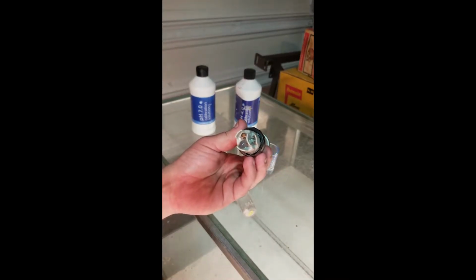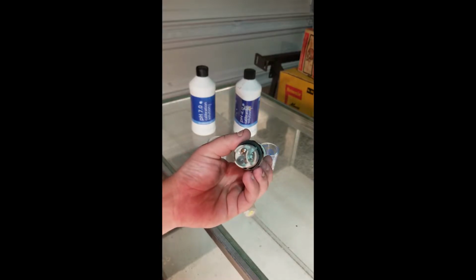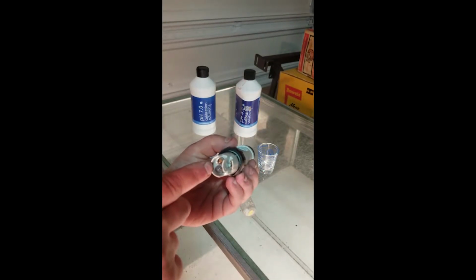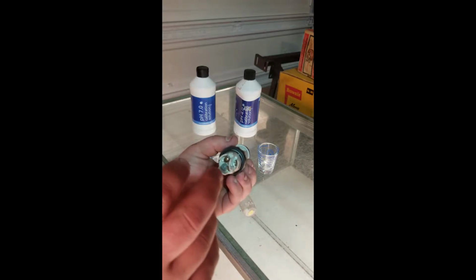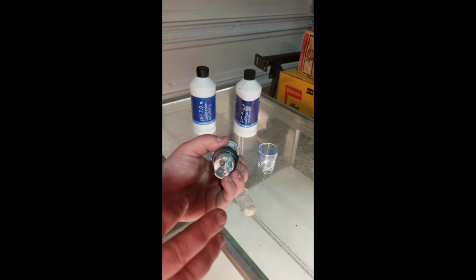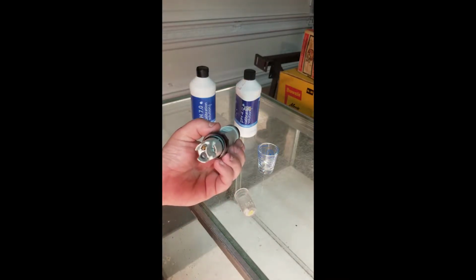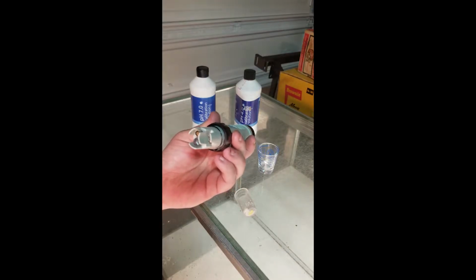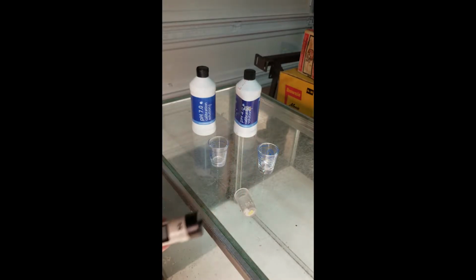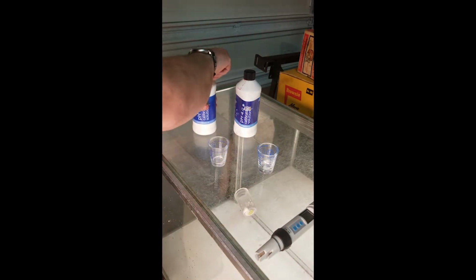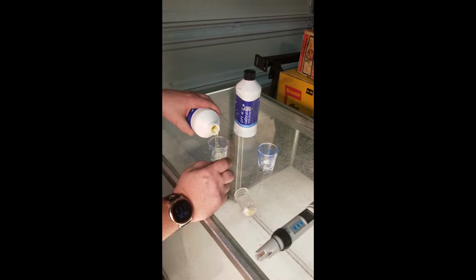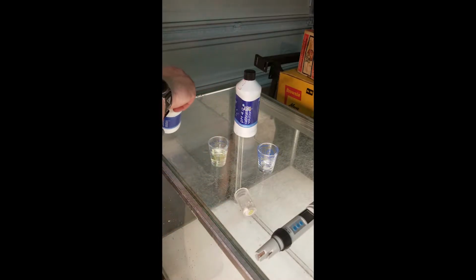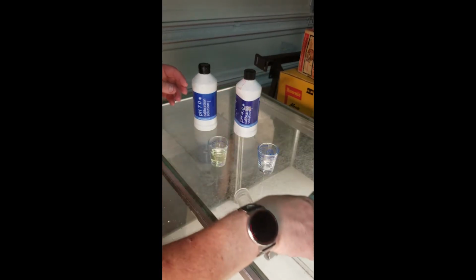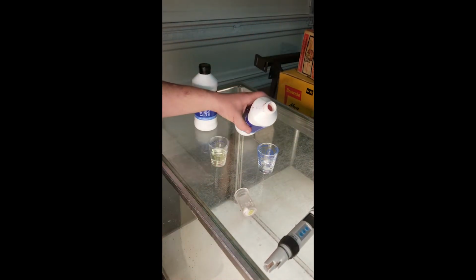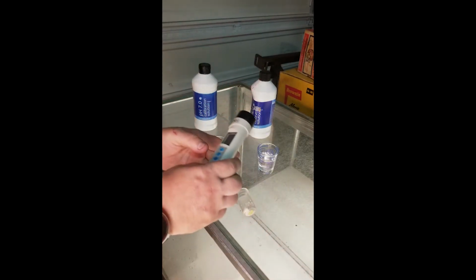First things first, make sure your probes are clean. You can take a very soft toothbrush to get any gunk that sometimes can get built up in the corners of the pH probe. Any physical media from slurry tests or anything like that can actually cause fluctuations and instability in the pH reading. So make sure you clean those tips really good first. Then I'll pour out a little solution that I'll discard in the end, enough to get good saturation so it'll sit down deep, of the pH 4 and the pH 7. They're usually yellow and red colored, so you know one is more alkaline and one is more acidic. Turn on your meter.